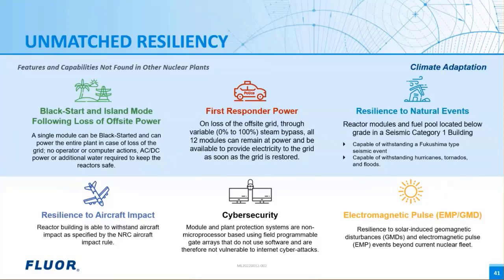As with all nuclear power plants in the US, it's designed to be resilient to aircraft impact. As I said, we take advantage of it being below grade to make it even more so for NuScale. And for cybersecurity, the NuScale plant runs on what are called field programmable gate arrays. So there's no software in the control system. Therefore, it's not vulnerable to software attack. And the logic for operating the plant protection systems is hard-coded onto these field programmable gate array cards. So you must be physically inside the plant to modify or change out that system. Additionally, the NuScale small modular reactor is hardened against electromagnetic pulse and geomagnetic disturbances beyond that of the current fleet.